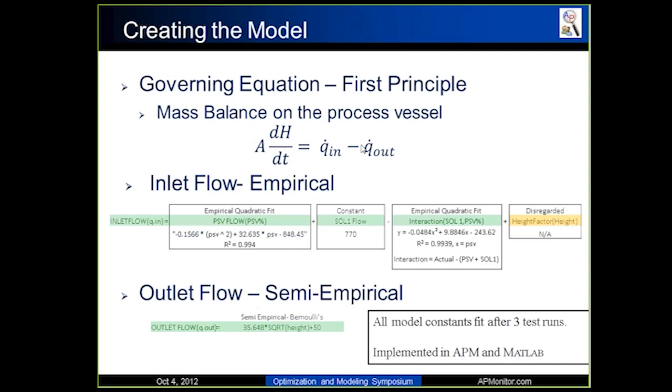However, the Q_in and the Q_out comes from a lot of empirical relationships. So the inlet flow is strictly an empirical relationship that I had to basically determine: how do you determine what the inlet flow is based upon whether the discrete valve is on and whether the proportional valve is on. It's basically got three terms in it. One is an empirical quadratic fit, which basically will give you the flow based upon how much the PSV is open, whether it's 100%, 80%, or 90%. And then SOL1 flow is just a constant because if you turn it on, it's always going to be that specific flow rate.